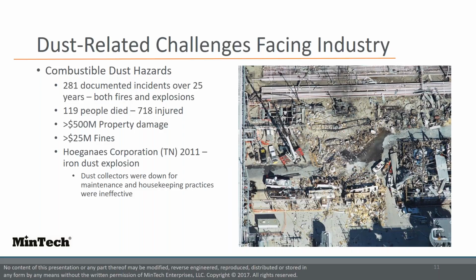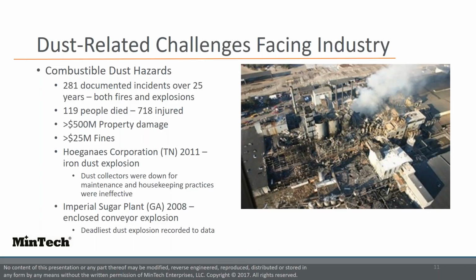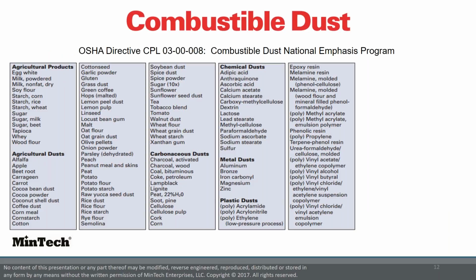Here are the details of just 2 of those incidents. 5 workers were killed in an iron dust explosion in Tennessee. At the time, dust collectors were down for maintenance, and no one was performing routine housekeeping practices to remove combustible dust from beams, ledges, or equipment. 14 workers were killed because of a sugar dust explosion at a sugar refinery in Georgia. The plant had a spillage problem when a chute was clogged, causing dust to be lofted into the air. Large amounts of airborne sugar dust reached explosive concentrations and were ignited, likely by an overheated bearing, which was most likely overheating due to, you guessed it, dust intrusion into the bearing.